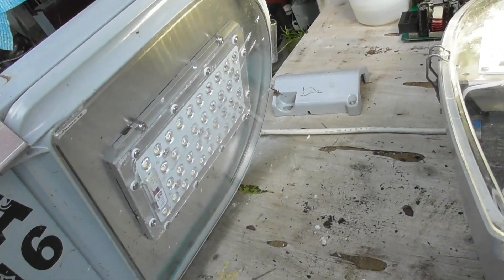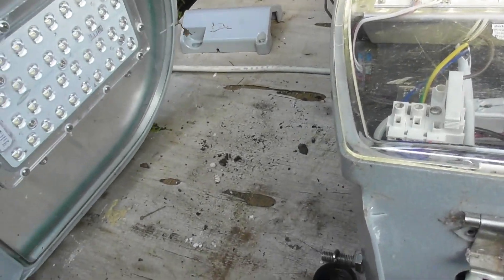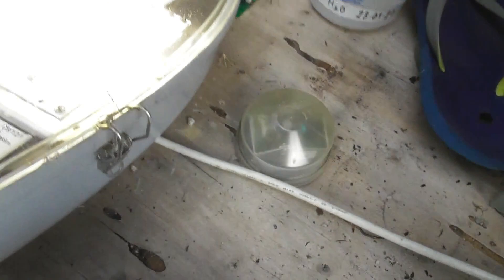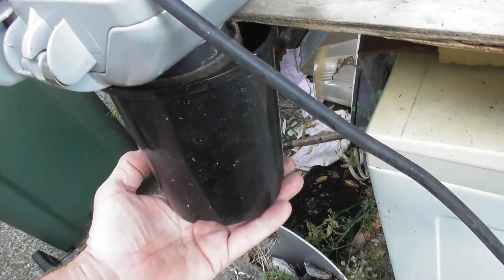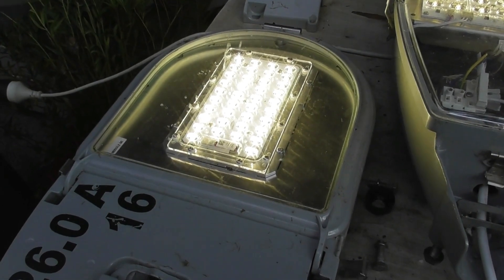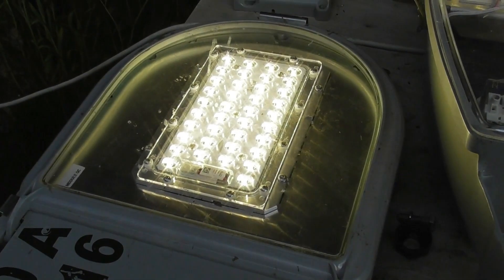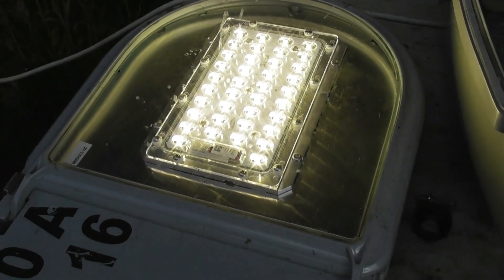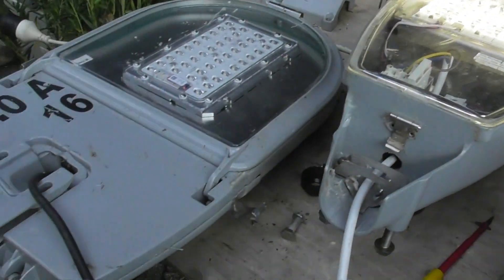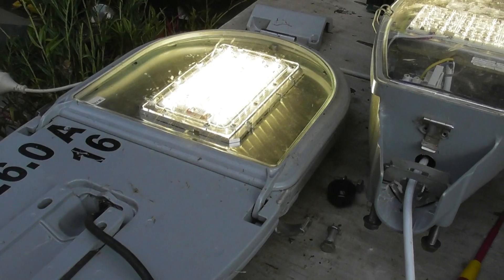The photocell is switching it off. Can you cover the photocell? It's a problem doing these one-handed recordings. I'll flip this thing over if I can. I'm going to hold a pot over the photocell and see if it clicks back on. There we go — quick response. Photocell is uncovered and it should switch back off again. I need to remedy that piece of wire and put some PVC covering over it. The light has gone off again, and covering it up gives a pretty quick response on this device.